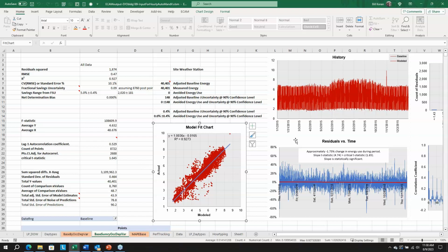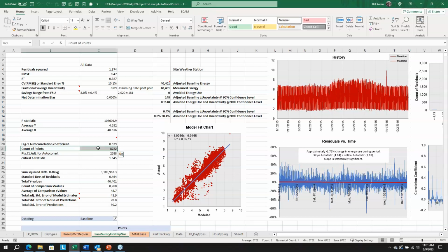One of the other important charts, which isn't as practical when you only have monthly data since you don't have enough data points, but with any interval data you can look and see if energy use is changing over time. That's the purpose of this residuals versus time chart. The residuals are the difference between the actual data and what the model predicted for an individual point in time. So all of the 8,760 hours in the year, or whatever I had in the baseline here, are reflected here. You can look and see if there's a slope to this fit over time, which tells you whether the energy use, after accounting for the independent variables, was changing over time.